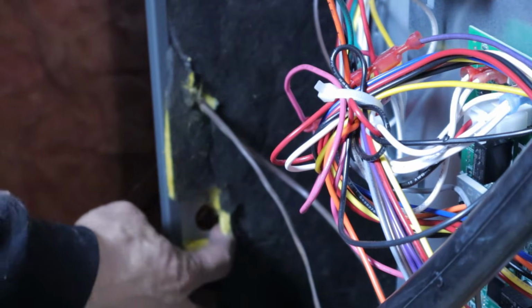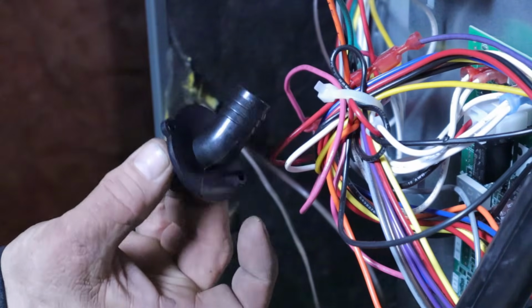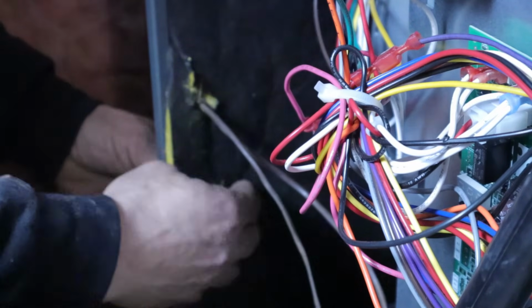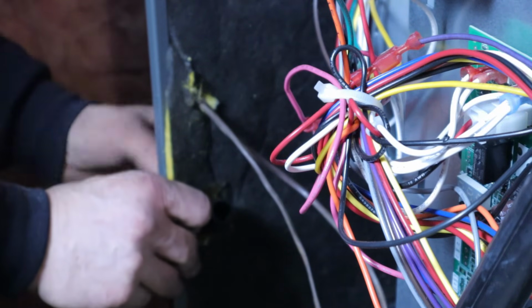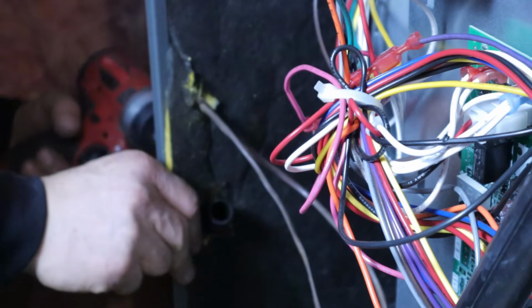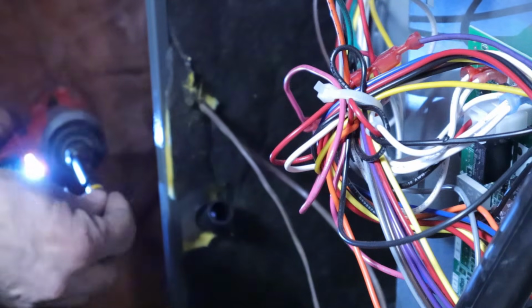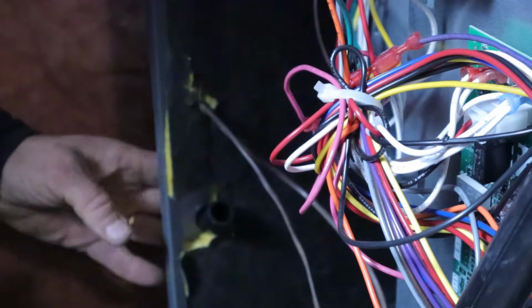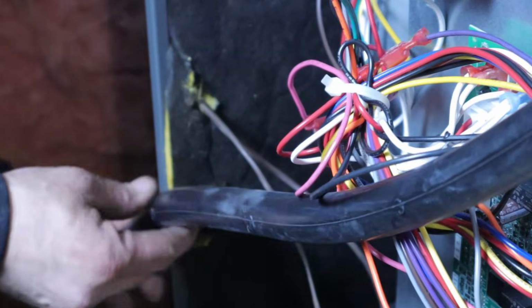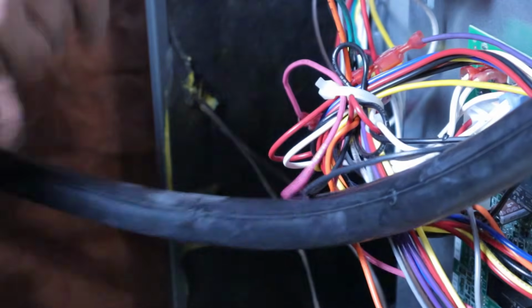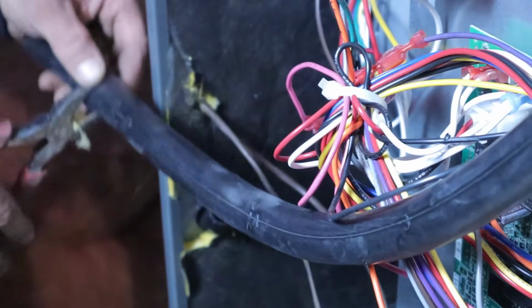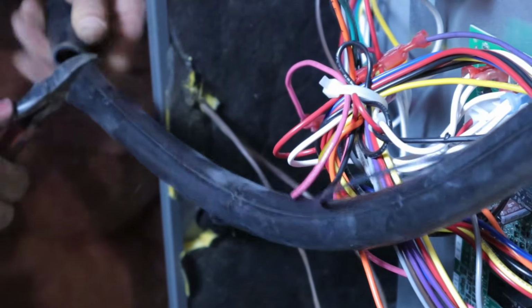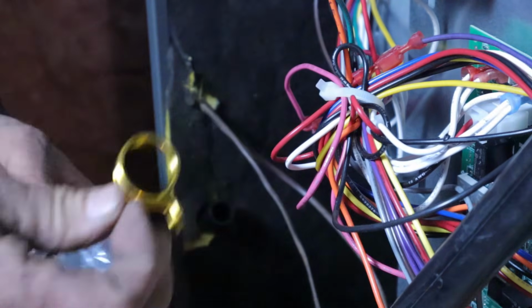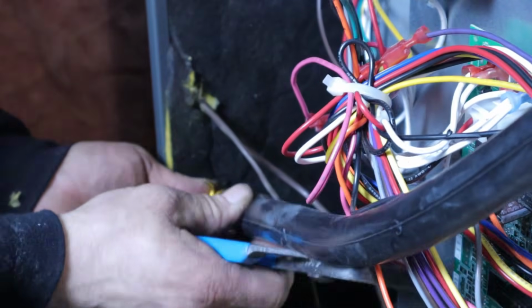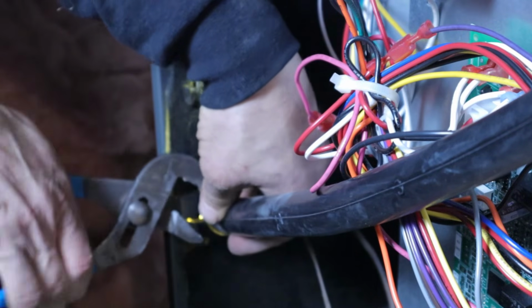So this is our knockout here down in the corner of the furnace. We're going to take this piece and we're going to feed it right in the side here, and this is where we're going to hook our hose up. So we're just going to take 2 screws and screw this piece onto the furnace casing itself. So now our fitting is secure on the furnace, it's not going anywhere. And we're going to take our tube, we're going to cut it to the right length, right about there. There's a gold clamp in here, and that's the right one for this tubing. I'm going to clamp that right onto the fitting. Sure, it's on there nice and tight. And there we have it.